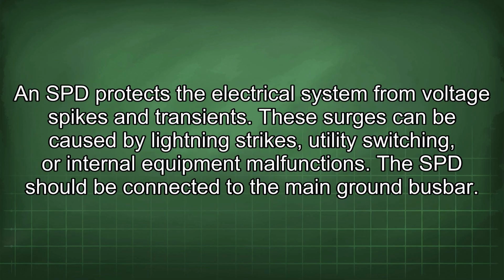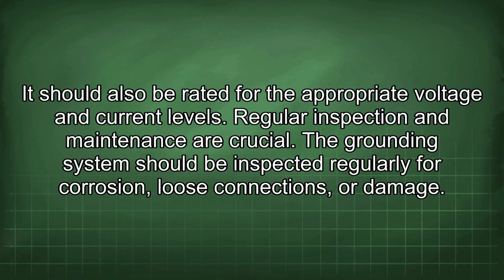An SPD protects the electrical system from voltage spikes and transients. These surges can be caused by lightning strikes, utility switching, or internal equipment malfunctions. The SPD should be connected to the main ground bus bar. It should also be rated for the appropriate voltage and current levels. Regular inspection and maintenance are crucial.